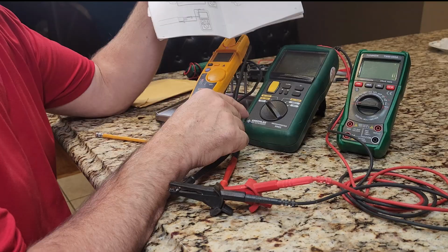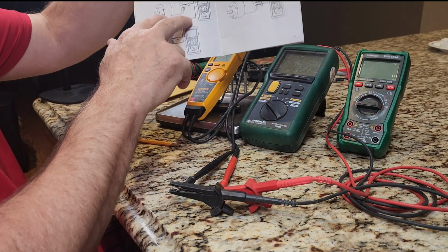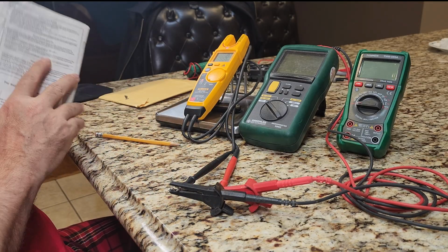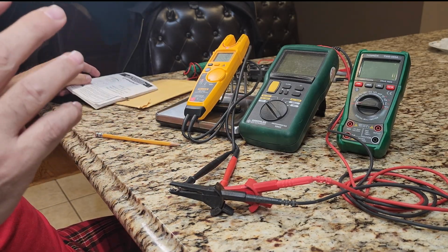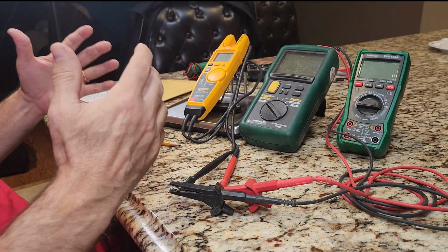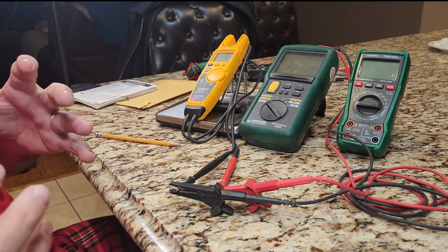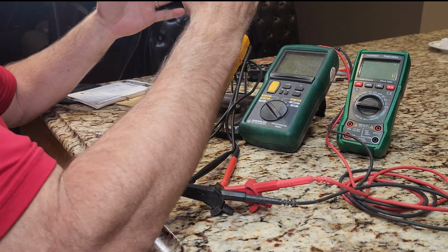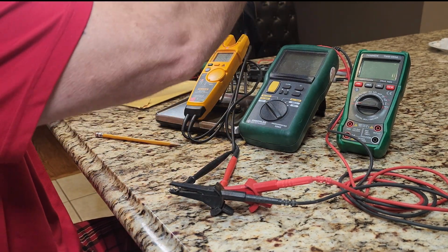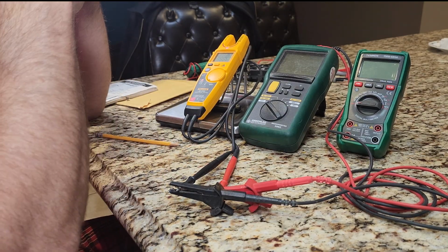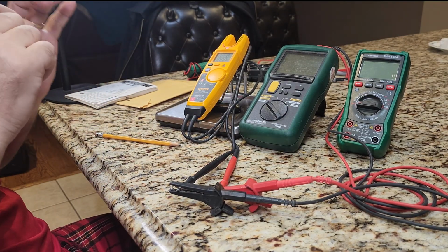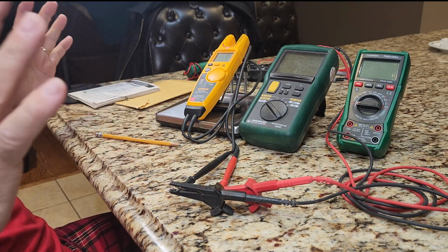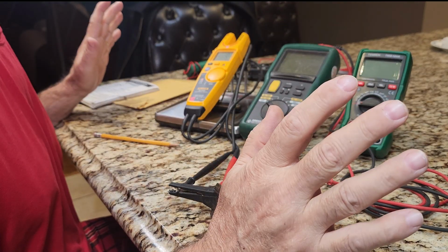You're going to test the insulation quality of a motor and on heavy wire. So let's say we've got 15,000 volt high voltage wire running from a switch into a low voltage 480 volt panel. We come from a sectional switch, and we run our underground, even if it's in PVC, from the 15,000. Boom, we pop up into our outside transformer. Well, we want to measure that high voltage wire before we even energize it or before we even start to splice it.